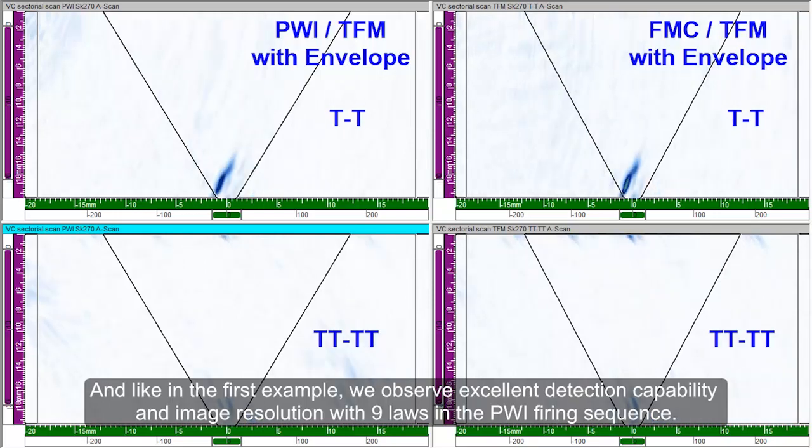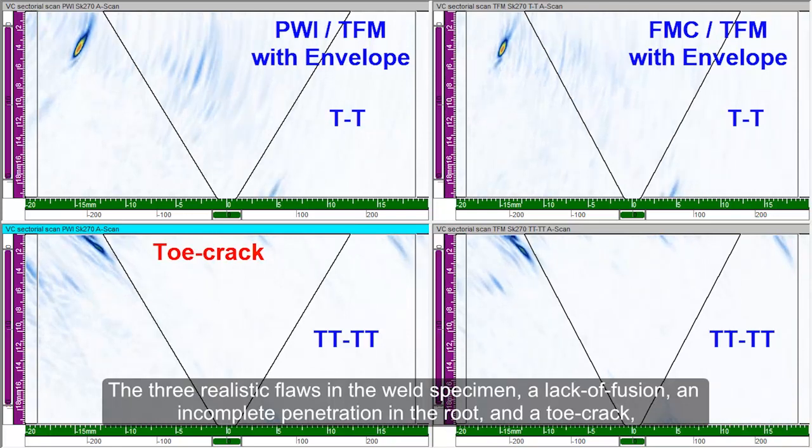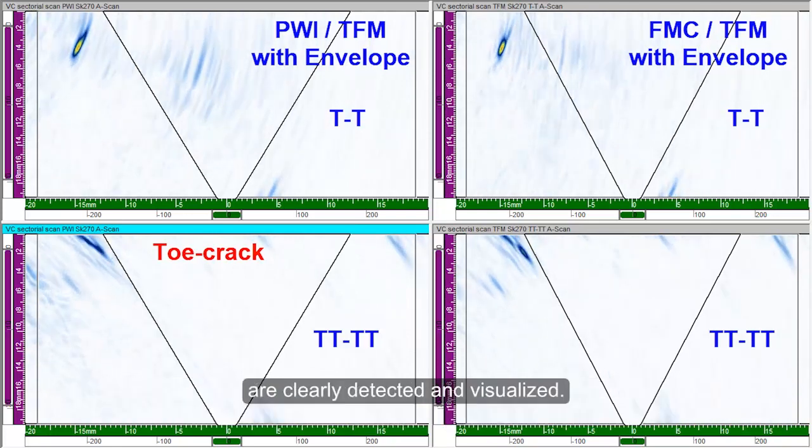And like in the first example, we observe excellent detection capability and image resolution with the 9 laws in the PWI firing sequence. The three realistic flaws in the weld specimen, a lack of fusion, an incomplete penetration in the root, and a toe crack are clearly detected and visualized.